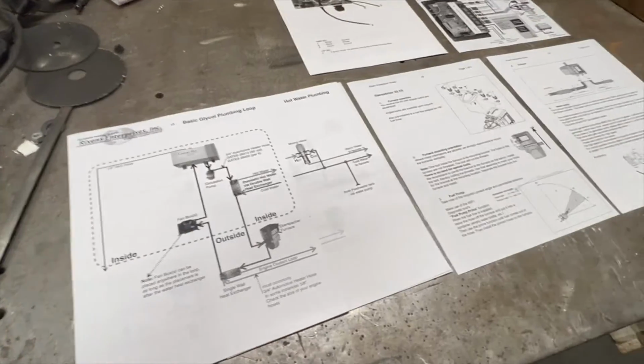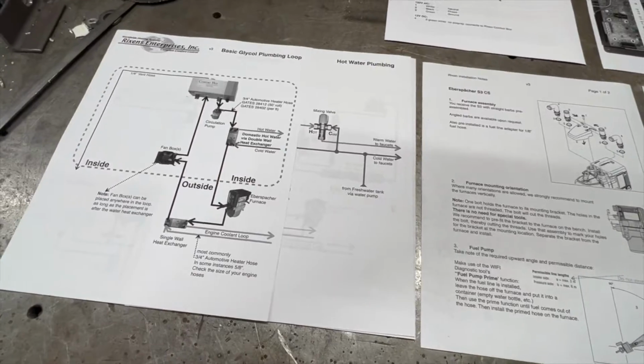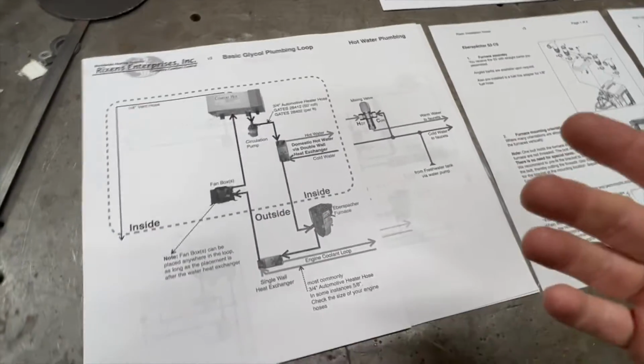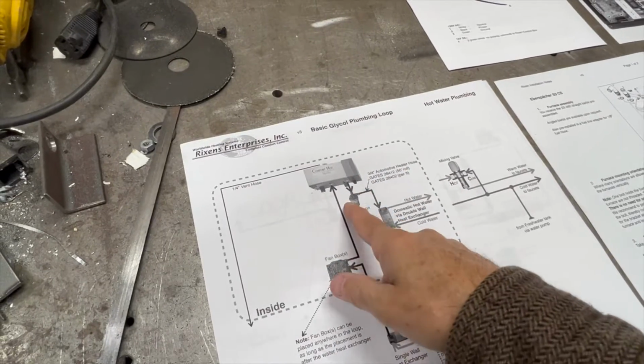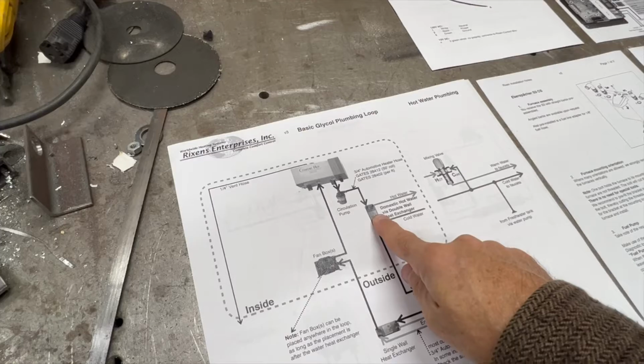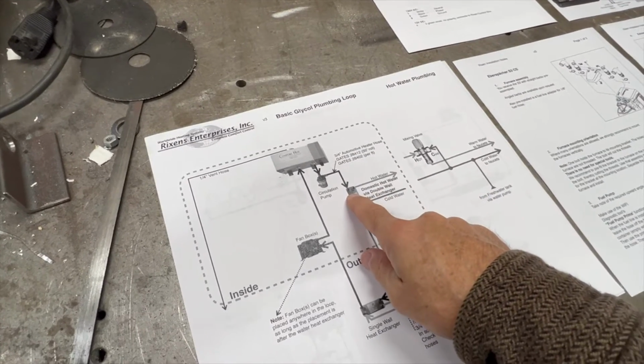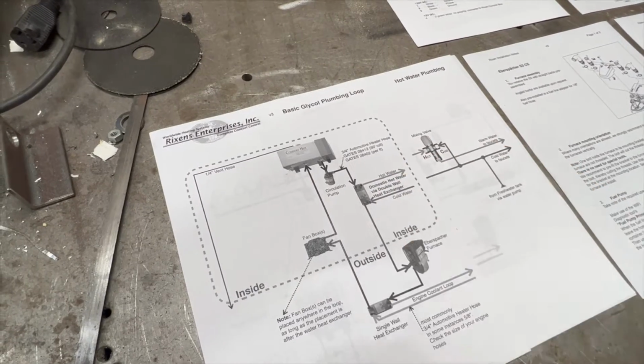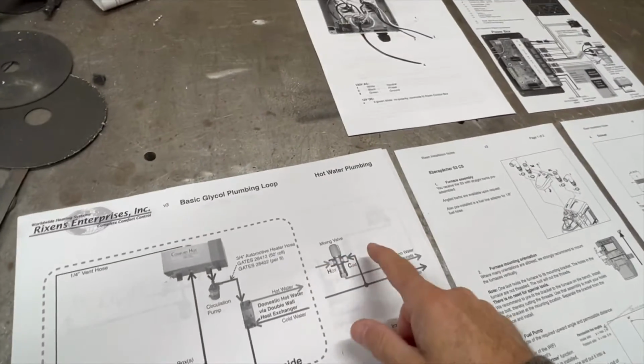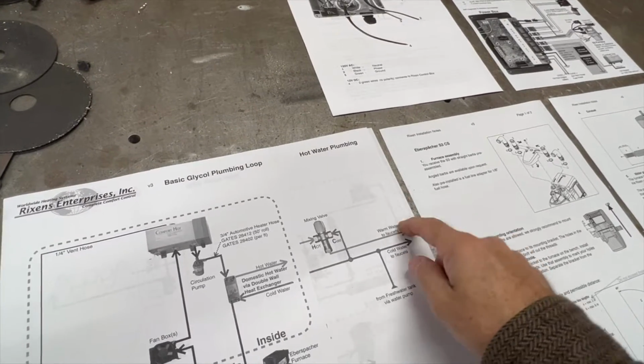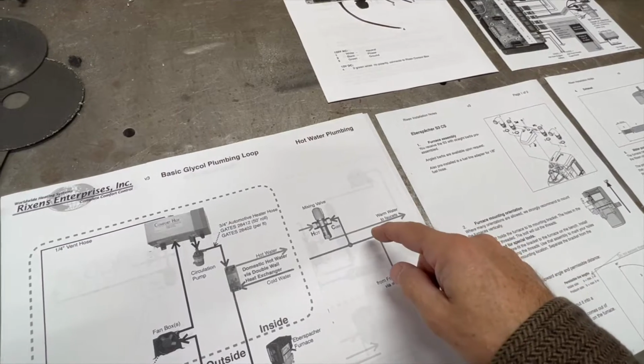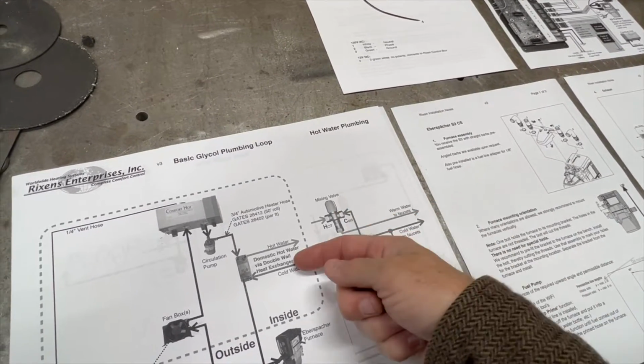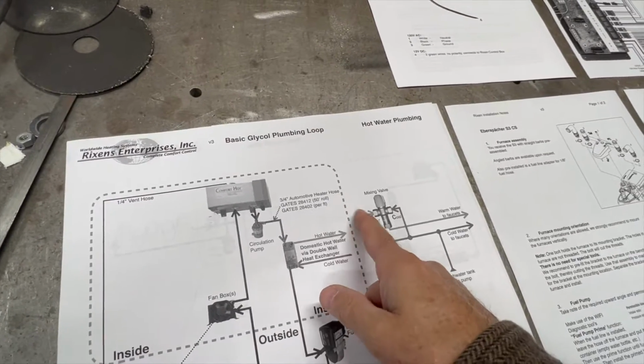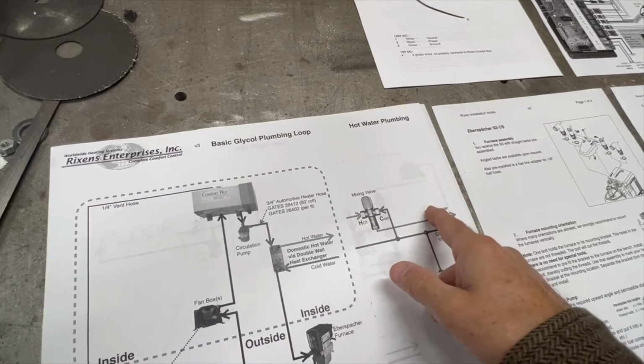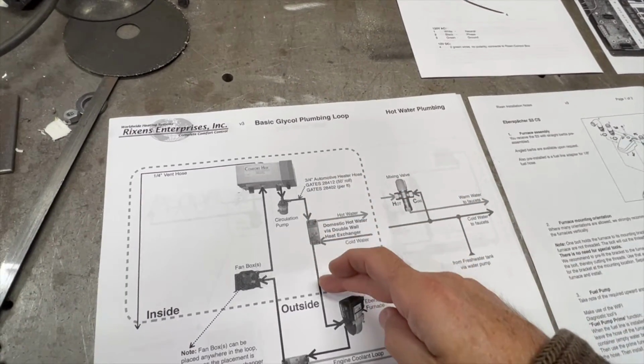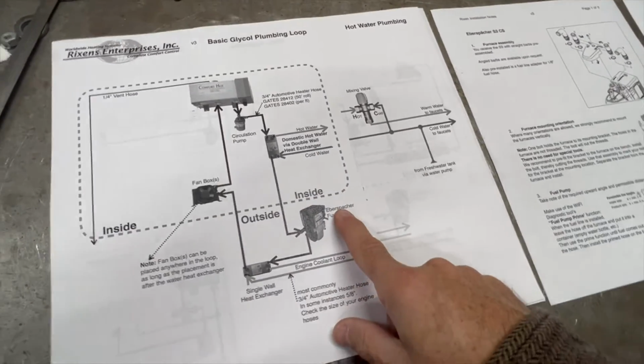Here's what I downloaded off the Rixen website, the things pertinent to what I'm doing right now. This is the plumbing diagram. Really, it's a big loop. You have your coolant expansion tank, down to the circulation pump, through the heat exchanger, which the double wall heat exchanger is used on the hot water or domestic water side. Run it through a mixing valve, off to the hot water side of your system inside the van. Cold water comes in and goes to this side of the mixing valve and into this side of the heat exchanger, coming out as hot water, back into the mixing valve with the correct temperature water coming out.